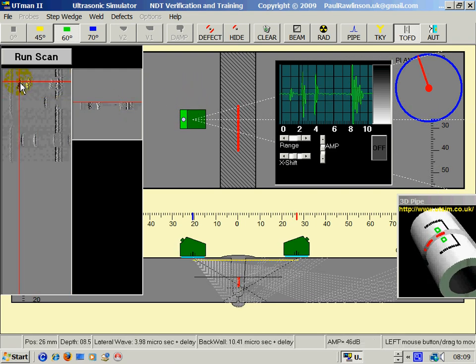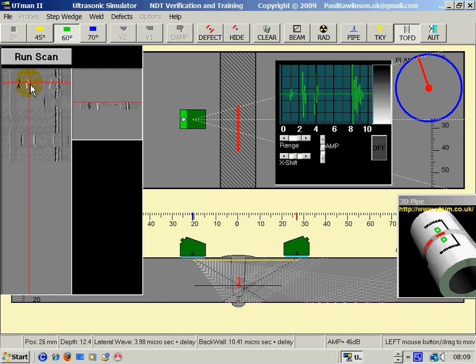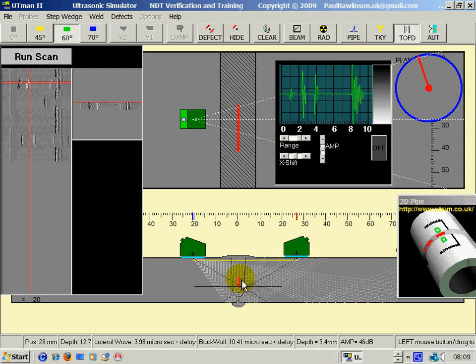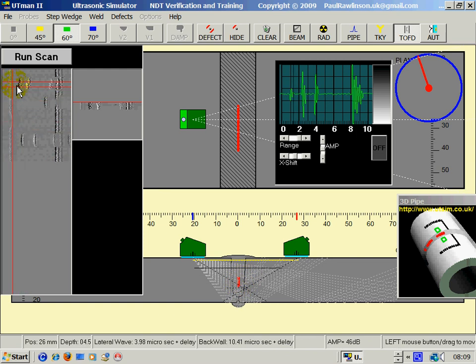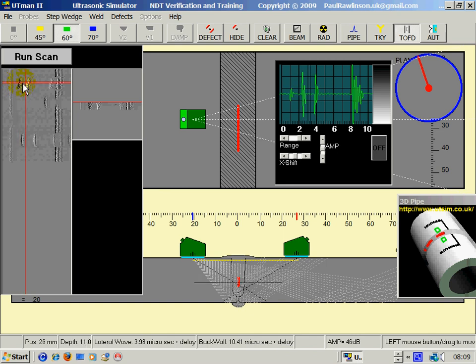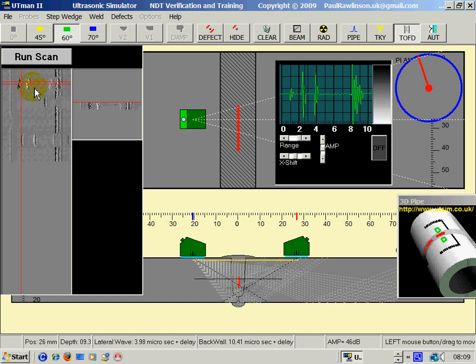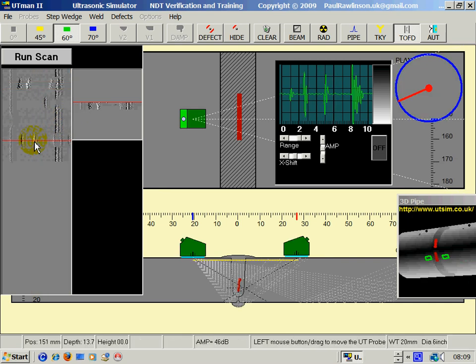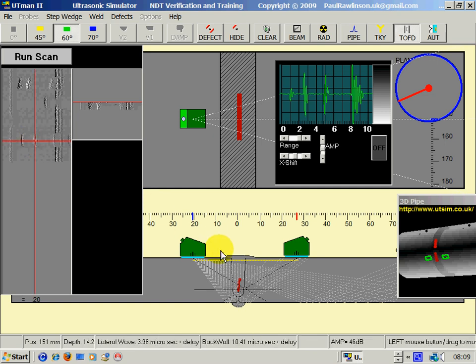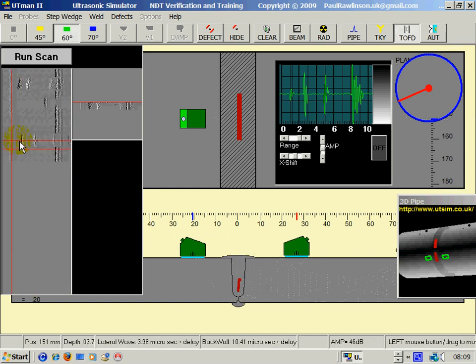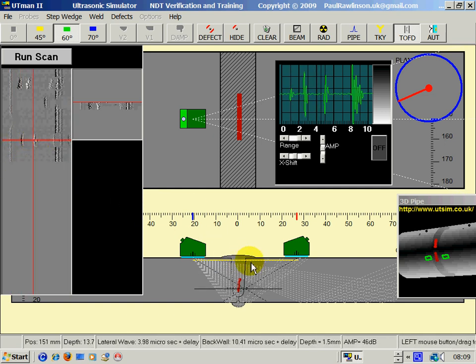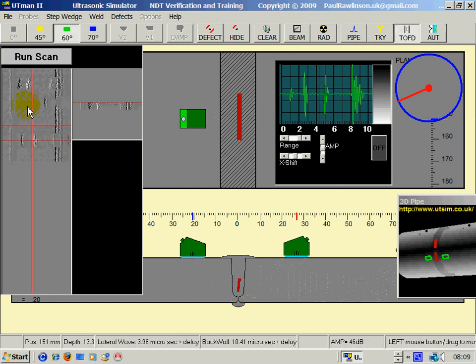We can see the top and bottom of the defect. Now, the concept of TOFD is it will only show the top and bottom of a defect. So we cannot see the bit between the top and the bottom. So here we can see the top and the bottom of this defect. The distance between them represents the height. And this one here. And this one here. We can see that we've got a top and a bottom here on the display, representing the top here and the bottom here.